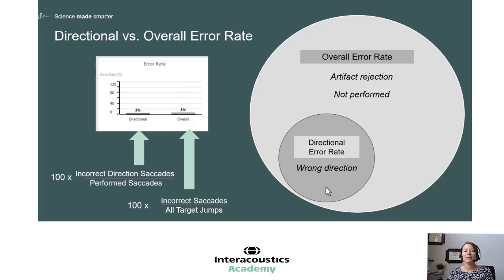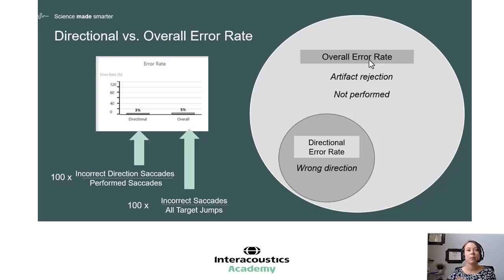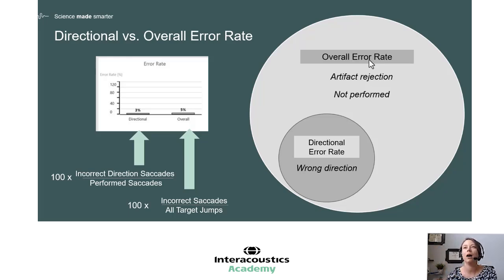The overall error rate not only includes the directional error rate — how many times people went the wrong direction — but also all artifacts rejected such as blinks, and all saccades that were not performed. Similar to spectral purity in rotational chair testing, it's a pulse on how valid or how noisy the response is. You wouldn't want a significant difference between the directional error rate and overall error rate. For example, if the directional error rate is 3% but the overall error rate is 90%, that means there's quite a bit of artifact rejection or missing saccades, and you may want to be very careful with interpretation.